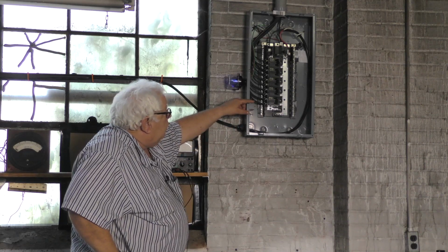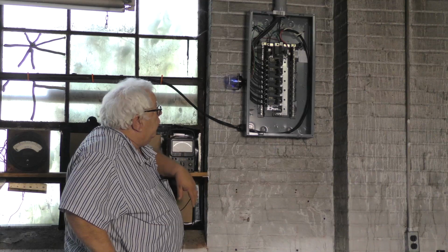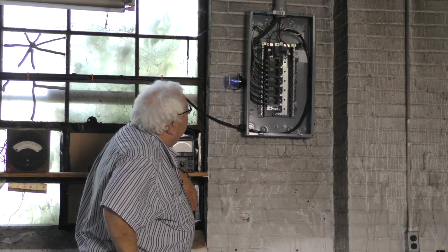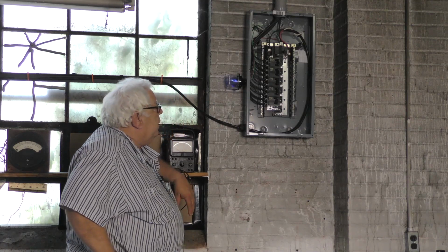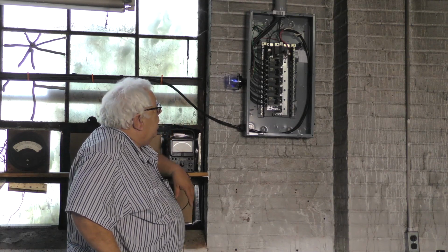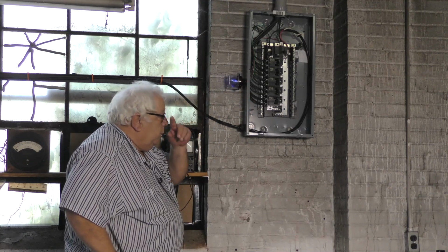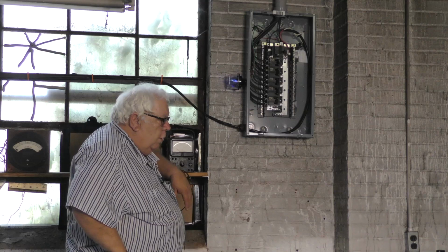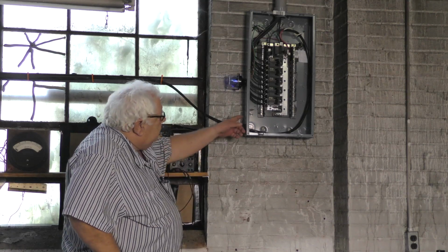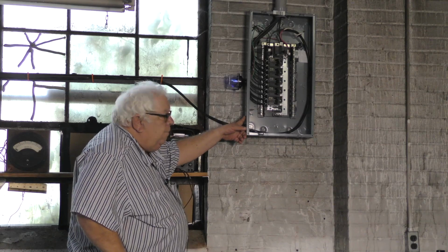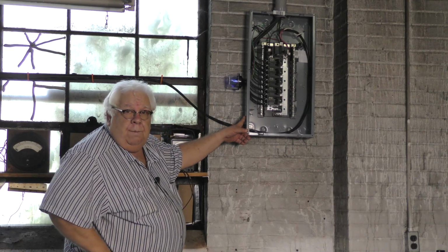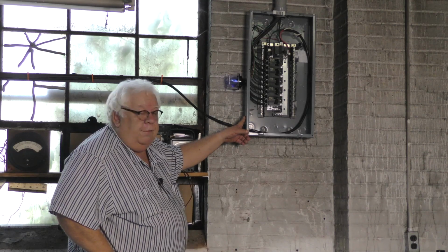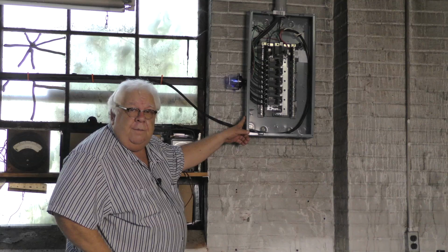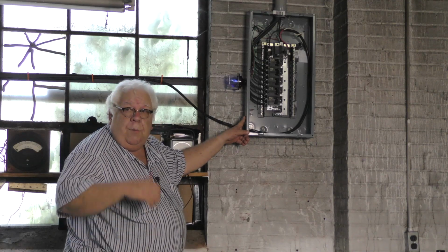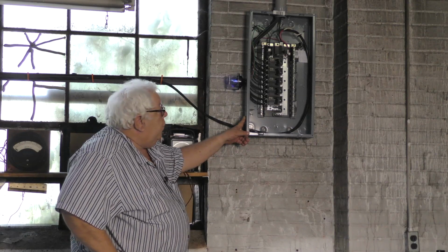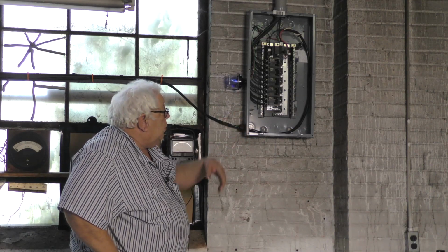And we put the 2 wires on 240 volt AC circuit breakers. I don't even know what these are, but it doesn't matter, a 20 would be fine, whatever you have. So we have 5 circuit breakers, 2 wires to each for 240 volts, and that applies to our loads panel as your house is designed. Your L1 and L2 are your 2 phases, it's actually 1 phase split. We get the neutral from our power system, not from the roof, and we have a ground coming from the roof.